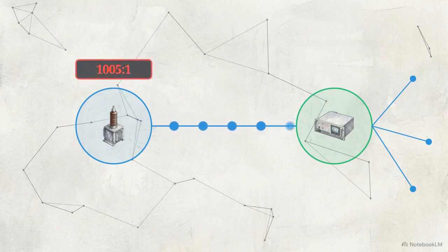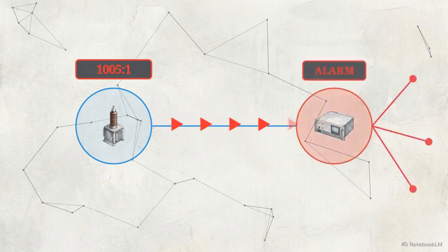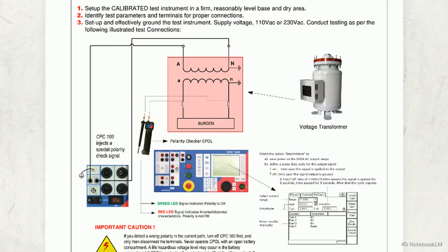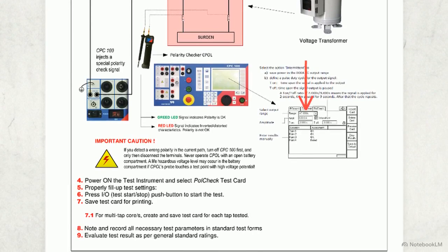Even a fractional deviation here corrupts the primary logic of downline protection relays, feeding them inaccurate data about the grid's actual state. A perfect step-down ratio is useless and highly dangerous if the secondary phase relationship is inverted. As detailed in the test diagram, the system uses a specific polarity check to prove phase direction. The CPC-100 injects an intermittent, sawtooth-style pulse signal directly into the primary terminals. The test card is configured with a strict duty cycle, typically applying the pulse for 2 seconds and then pausing for 9 seconds to allow the secondary response to reset.